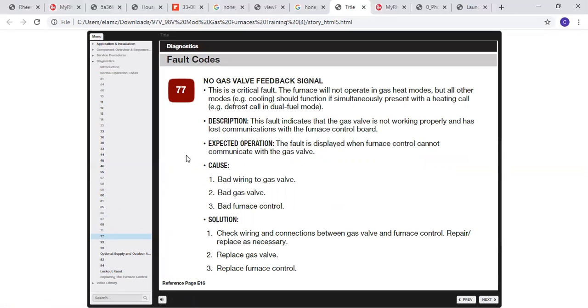Code 77, you have a no gas valve feedback signal. This is a critical fault. The furnace will not operate in gas heat modes of any kind. It will still work in cooling. We have some videos, which I'll show in a few minutes, on different ways to diagnose and troubleshoot various aspects here. In this case, if you have no feedback signal, it could be bad wiring to the gas valve, a bad valve, or a bad control board.